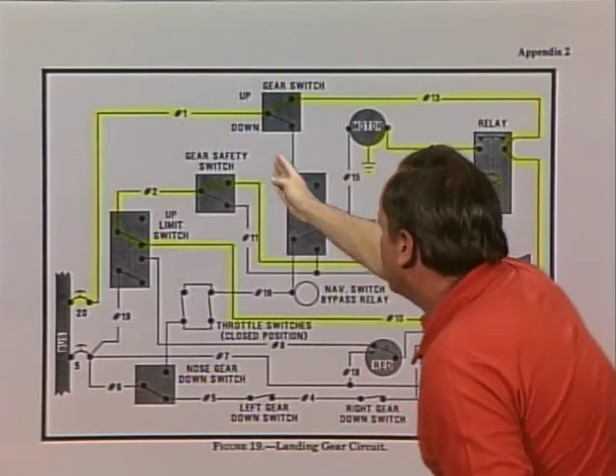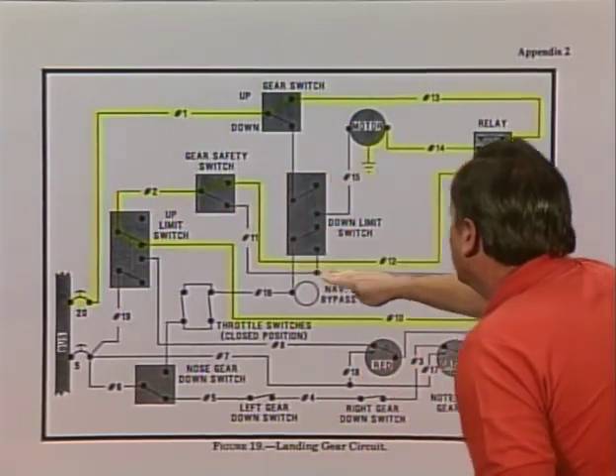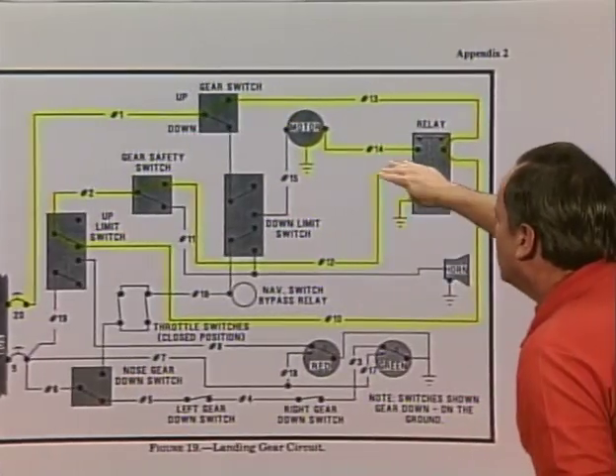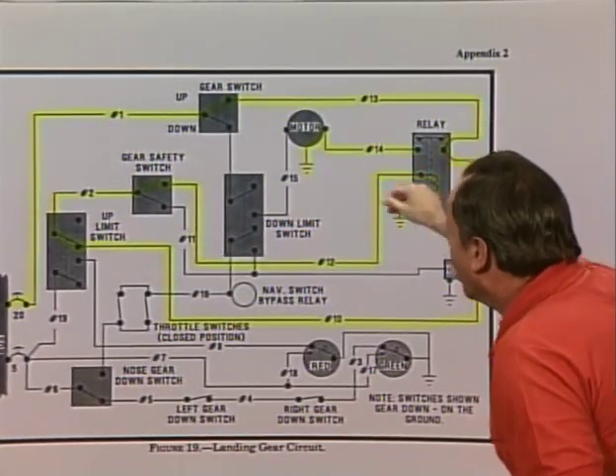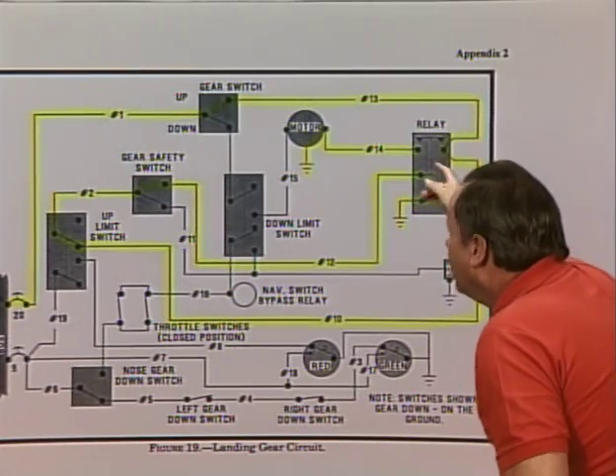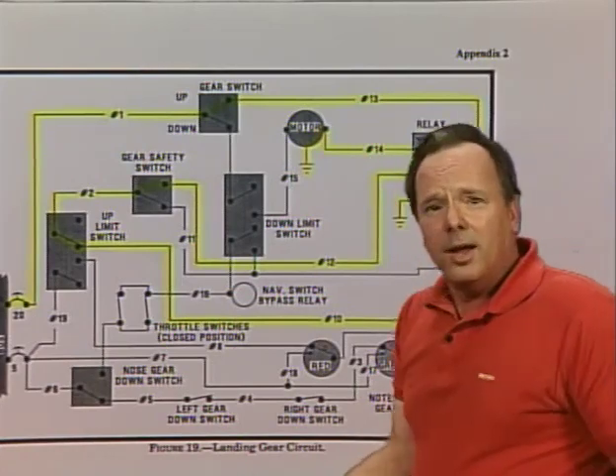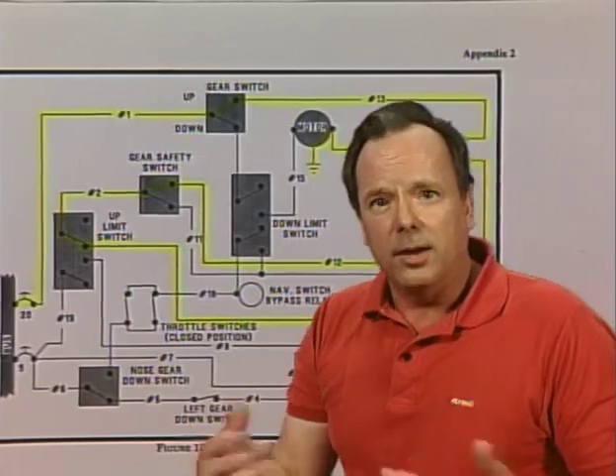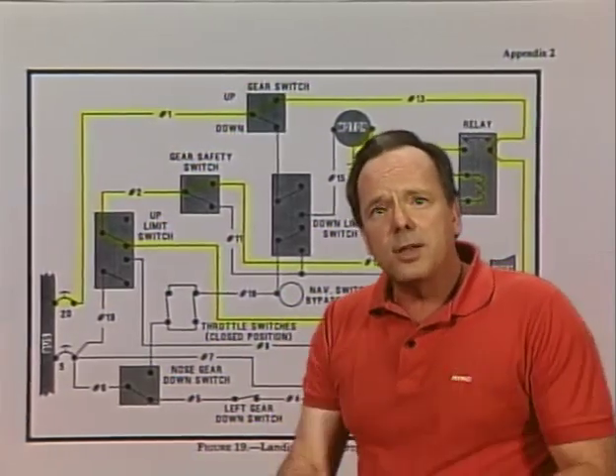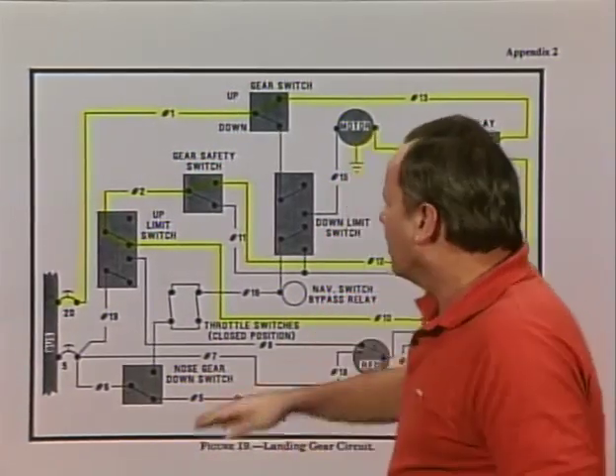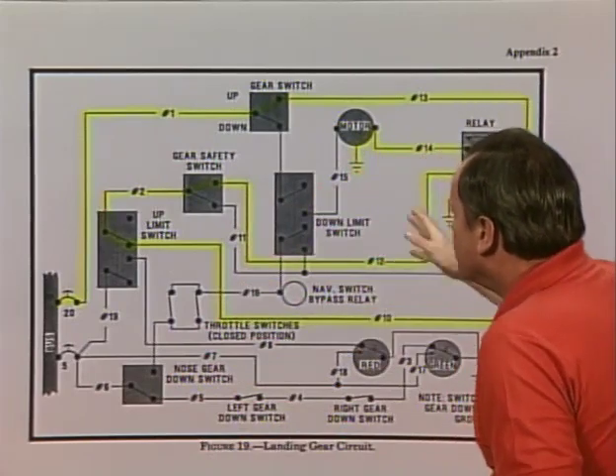So we'll now have a path for the current to go through here, and the current will go right through here, and that's what's going to close the relay, then goes to ground, and that's what's going to close the relay to make the landing gear motor work until the gear is up and locked, and of course then the relay would be open. So you can see that that is the path that we would need to follow right there, and these are the wires that we need to check.